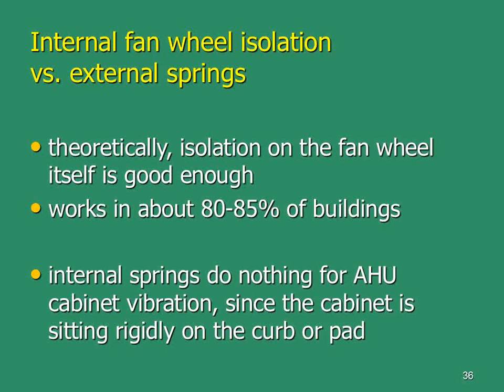Or if somebody thought a little bit about the possibility of noise or vibration-induced noise, it might be bolted through rubber pads. Now, rubber doesn't isolate below about 300 hertz. So everything below 300 hertz, that may as well be a 2x4 block. And remember, I just said transformers are 120, 240, and 360. So you're into the second harmonic before those pads even begin to work.